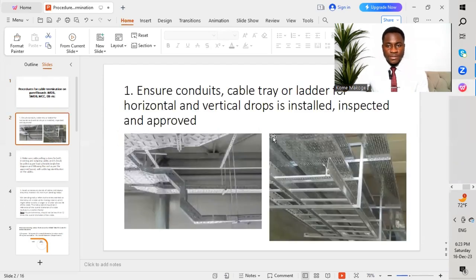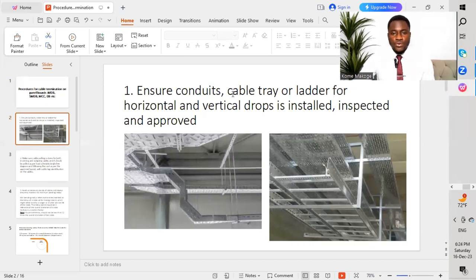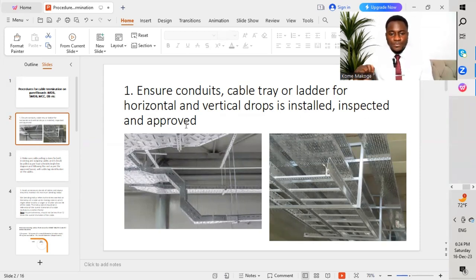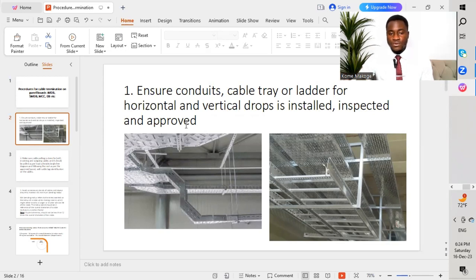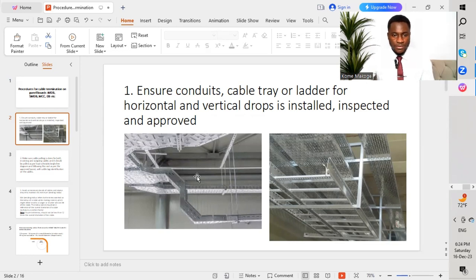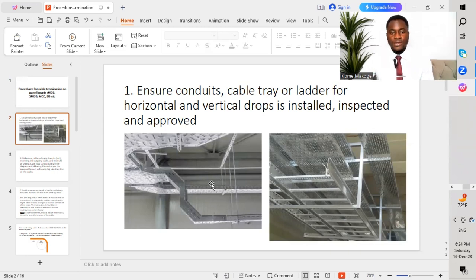The first point: ensure conduits, cable trays, or ladders for horizontal and vertical drops are installed, inspected, and approved. We have to ensure that our containment works are completed prior to proceeding with cable installation. We get the shop drawings approved by the consultant, then move to site and start the installation of the different containment services. Once done, we get an inspection and approval, then proceed with cable pulling.